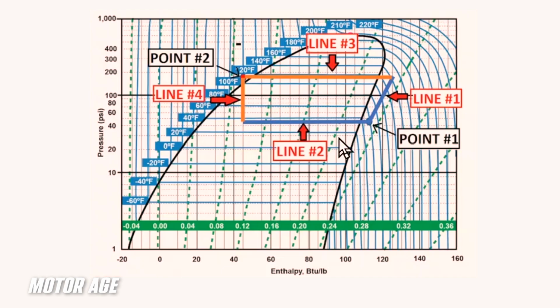And the significance is where these lines are plotted and how they intersect each other, relative to this bell curve. This really holds significance to the operation of the HVAC system and its performance evaluation, if you will. In other words, we can look at this and get a visual interpretation of how well the refrigerant loop is doing its job, or how hard it's working to do its job, or if it's not doing its job properly at all. And we can do that without the typical approach to HVAC diagnostics.